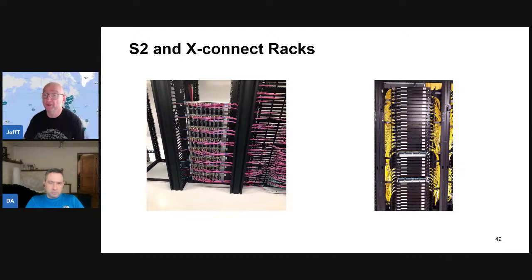At Microsoft, we've got 4 different locations, which we call ADF, where we place T2 or super spines that are responsible for every plane. Yeah, because if it's only 1 or 2 switches in the rack, it's probably feasible to keep them in the same environment, more or less. But if it's really a lot of high-density boxes, and switches are not particularly good for airflow, because the entire front plate is basically occupied by transceivers, you don't have enough space for air to flow through, so they really need somewhat better cooling than a typical server.